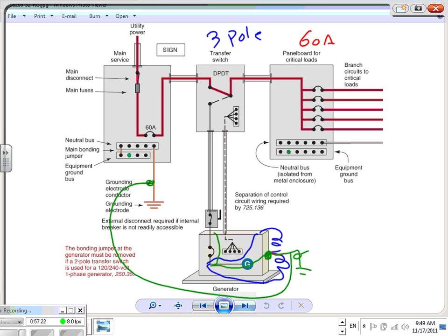That's your separately derived system. Do I have to do it this way? Can I run with a non-separately derived system? Yes. What's the difference, guys, if that was a non-separately derived system? The difference is right in here. Can you guys see that little wire here? You still need to see that bonding.